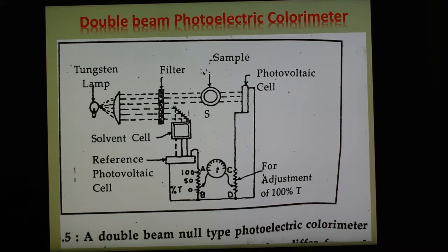The potentiometer dial is adjusted to read 100% transmittance, and then the slide wire contact R1 is adjusted to null the galvanometer. The standard and the unknown solution are introduced into the measurement beam, and the wire contact is adjusted to re-null the meter. The transmittance or absorbance can then be read from the potentiometer dial.